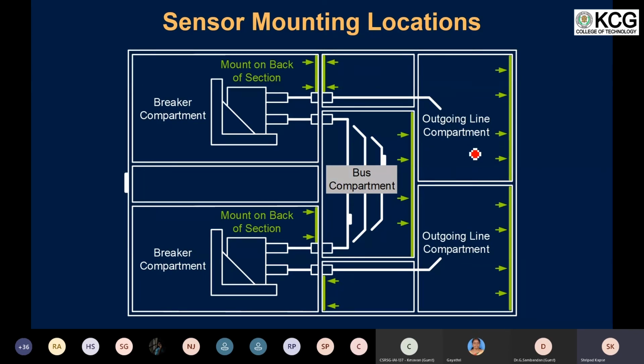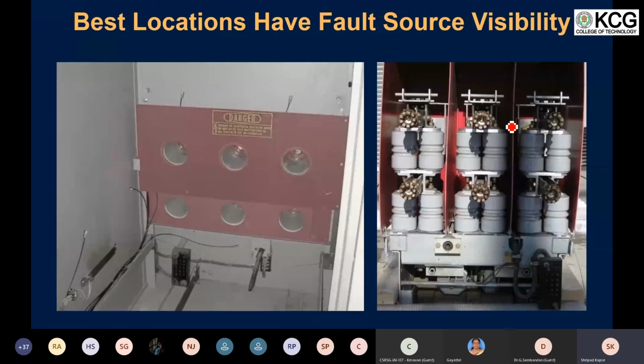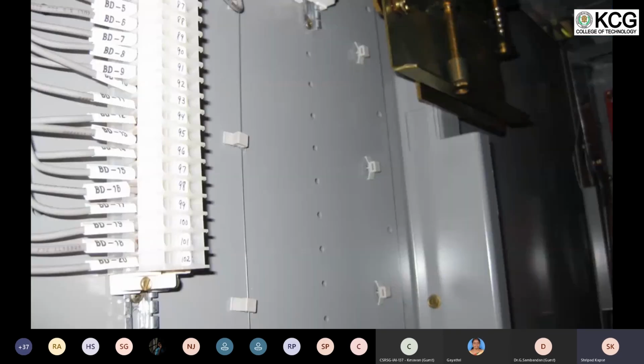Some of the ideal locations for placing this sensor would be in the breaker compartment. You can see on the top side or on the bottom side of the breaker compartment, and then this is the bus bar compartment. In the bus bar compartment you can mount them, and even in the outgoing compartments we can mount these sensors. These are some pictures from the actual installation of how the point sensors are mounted. These are some of the best places, the good places, and the suboptimal places to mount this sensor, so that these sensors can detect the light whenever a fault occurs, either during racking in or racking out of these breakers. And this is the installation of bare fiber sensors that we can see in the bus bar chamber.